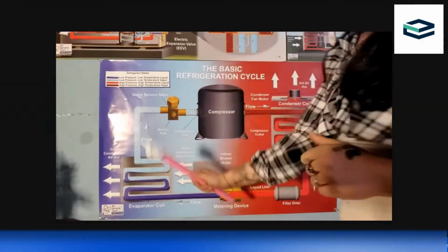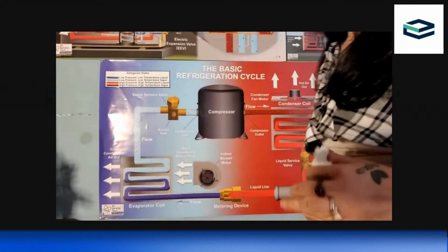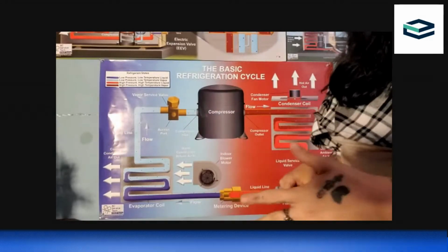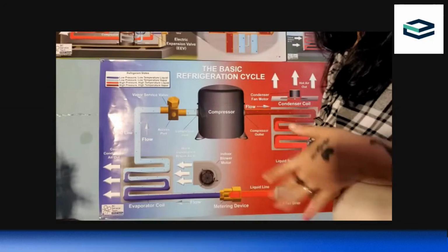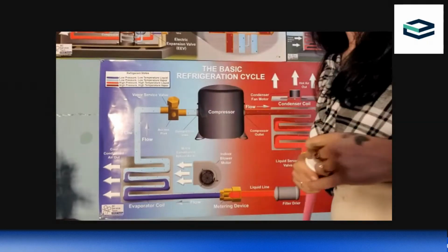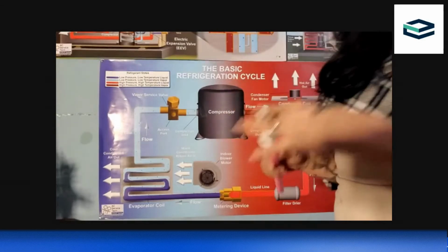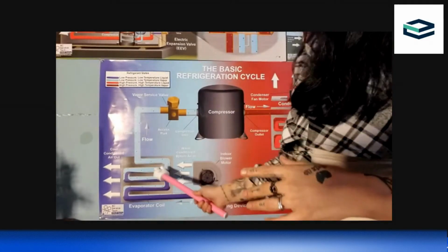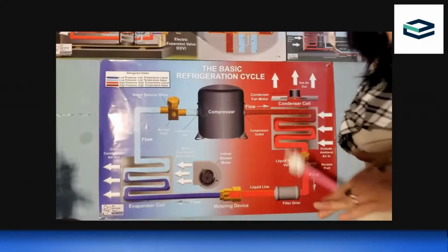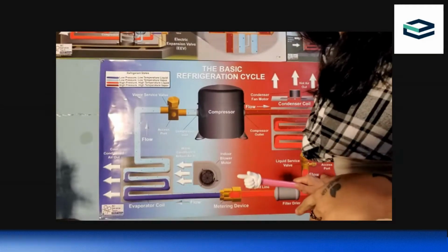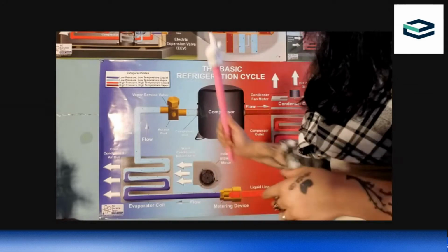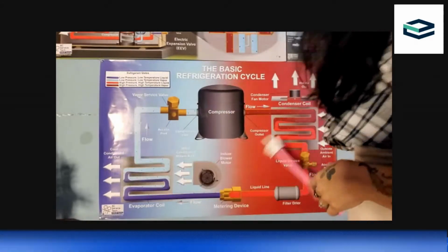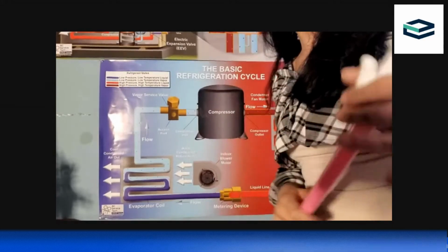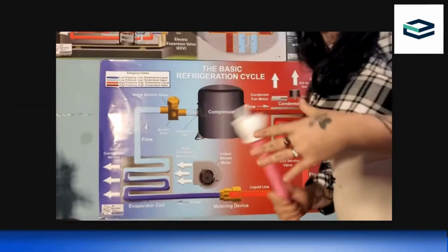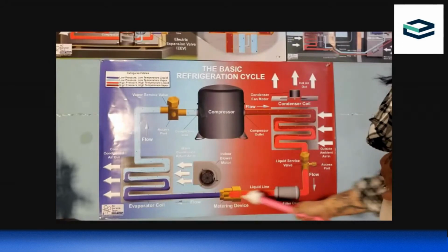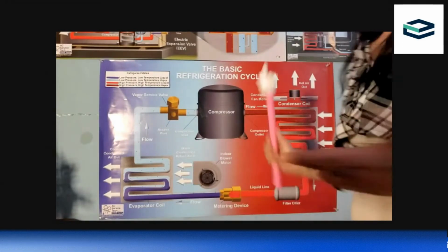But when you gauge up and you put your temperature clamps on, it will tell you your superheat and your subcool. For a 410A system, we really want to see around 10 for your superheat, and I say my sweet spot for subcool is around 14. It's going to vary again, but if you have a 2 superheat and a 50 subcool, then you've got too much liquid in your system, right? And if you've got a 50 superheat and a 2 subcool, you've got not enough refrigerant in your system. So it's either because it's trapped behind something like this TXV, this metering device, or it's just not there to begin with.